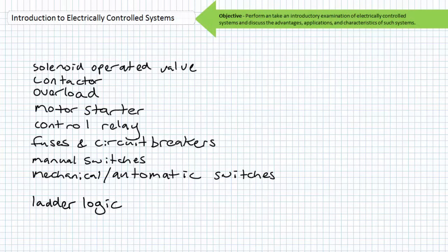Additionally, we introduced the programmable logic controller, which is largely replacing hardwired relay-based ladder logic, but interestingly enough, is still programmed using symbols and techniques largely identical to relay-based ladder logic. The principal difference between these two methodologies is that hardwired relay-based ladder logic must be physically rewired to change the functionality, whereas PLC-based systems can be simply reprogrammed to change the functionality of the system. We discussed the logical AND operator, the logical OR operator, and had a brief discussion about troubleshooting electrically controlled systems. Remember to review these concepts as often as you need to really drive it home. Imagine how well lab will go if you know what you're doing.